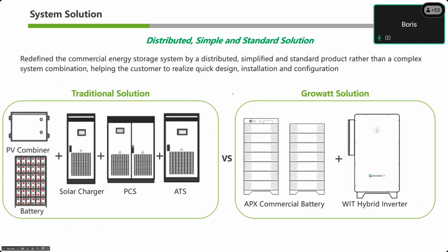Moving on. So the WIT is a lot like the SPH. Just like the SPH pulls all the equipment internally and, for example, has a transfer switch internal, the WIT does the same. So our goal with this product is to make installation as easy as possible. We're trying to remove the need for 5 or 6 different pieces of equipment. We want to just have it all located in one thing. You have quick connections between them, and then you can pretty much just plug it in and run it. So that's what the inverter does. It has an ATS internal. I'll show that later on. It has MPPTs internal, and then we offer the battery that connects directly to the WIT.